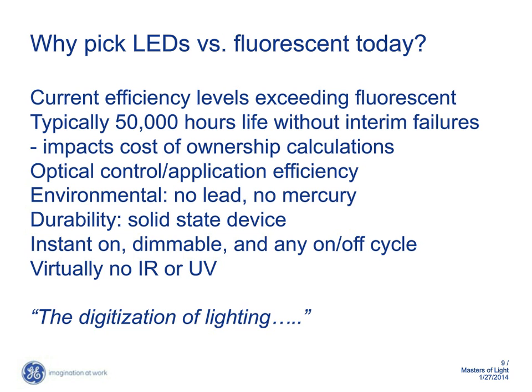Fluorescent systems today can last 80,000 hours or more, but you expect half the lamps to have failed by 80,000 hours. That's how we define average rated life of non-LED solutions. And in the case of LEDs, they get dimmer over time, but we don't really expect them to fail. So again, that affects your cost as you don't have to necessarily relamp failed lamps and the labor that it takes to do that.